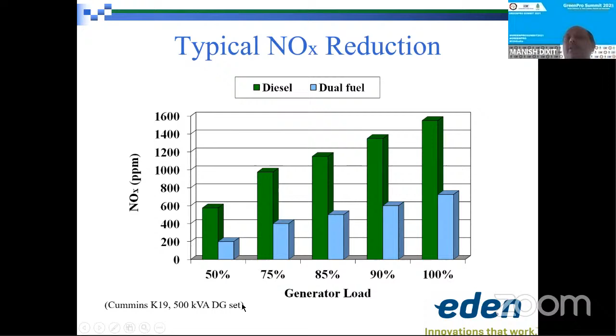So in terms of economics it's okay, but what about my greenhouse gas reduction? If I run an engine with 100% diesel versus the same engine run on dual fuel, you save something like 40 to 60% on different loads. I've given different load patterns here for a 500 kVA Cummins diesel genset, with savings on NOx and significant CO2 savings, from 100 metric tons up to as high as 700 metric tons on different engine ratings.